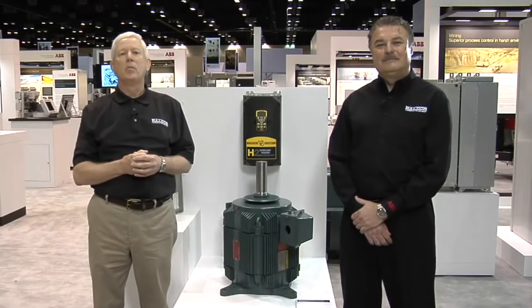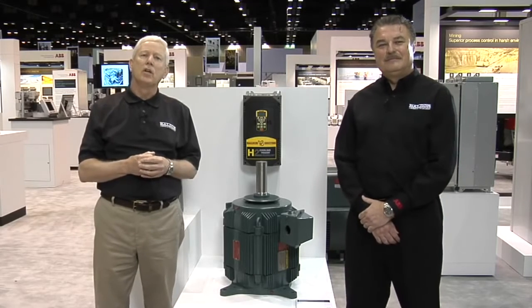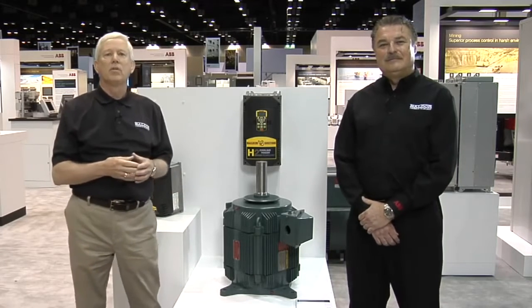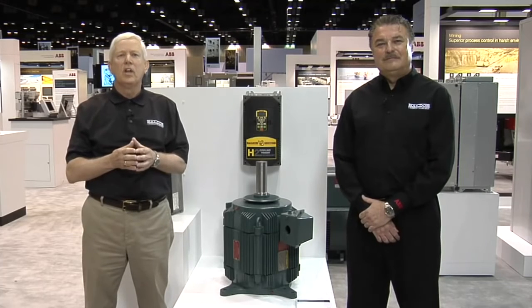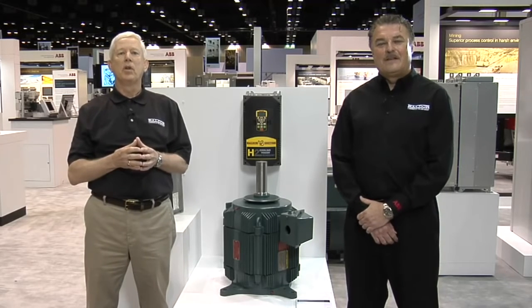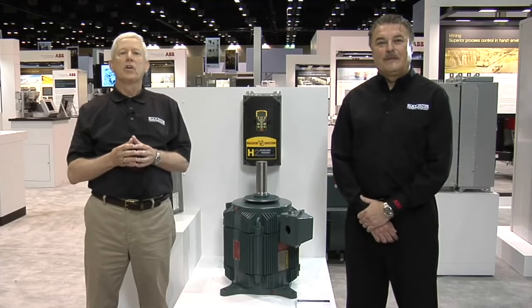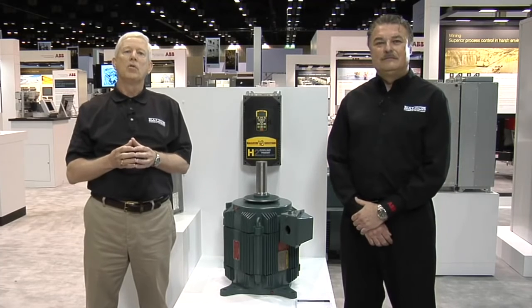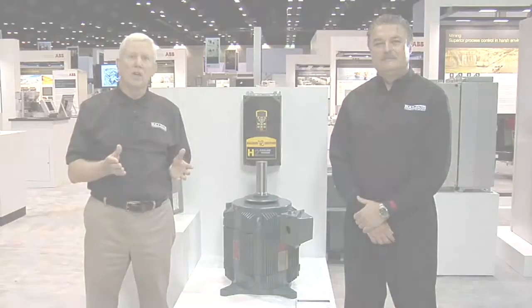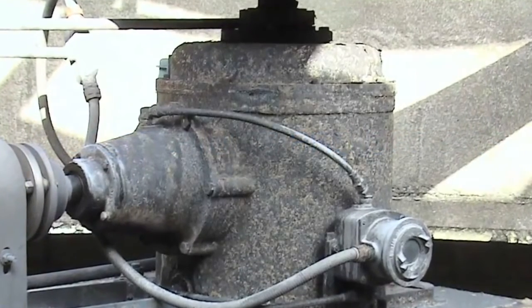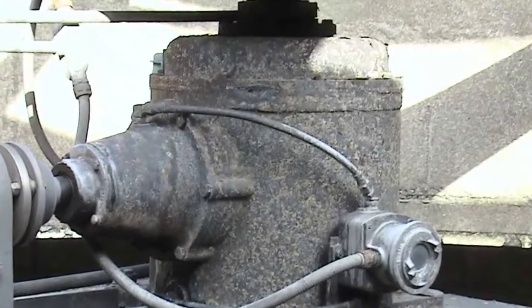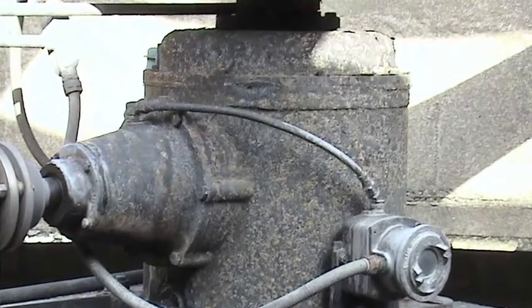After several years of development, we came up with a solution that not only reduced maintenance, but also created several other big benefits. In this video, we're going to talk about the solution: replacing your right-angle gearbox with other components, a newly designed motor and variable frequency drive, or VFD. The typical cooling tower includes a horizontal NEMA motor connected to the fan via a drive shaft, disc couplings, and a right-angle gearbox. That mechanical drive system is a source of constant maintenance headaches in many applications.